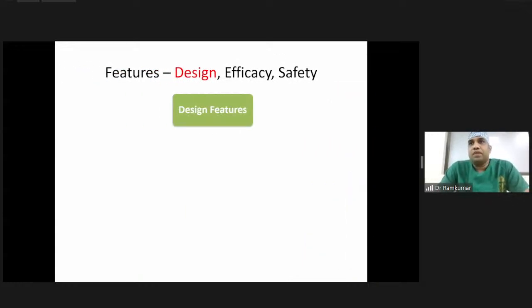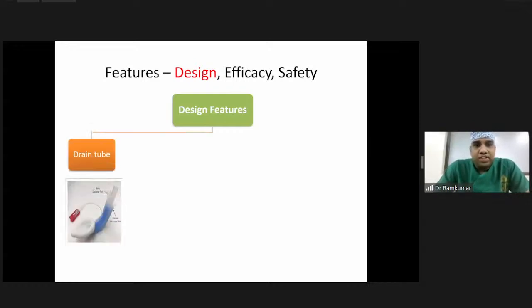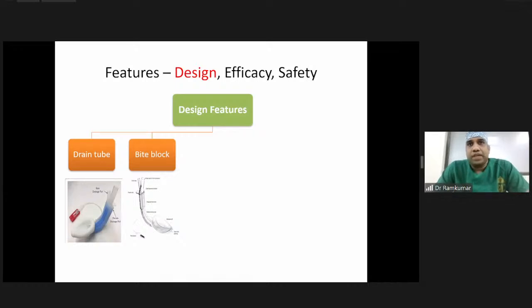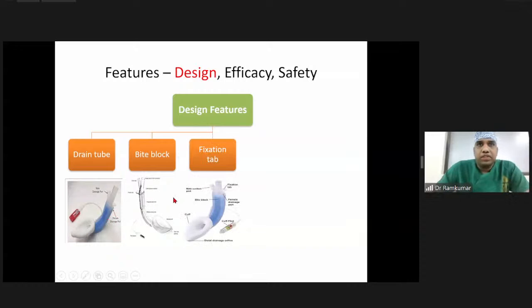What are the features that help to achieve this? Very useful. Coming to the design features, the drain tube: with the drain tube we can reduce the risk of aspiration and reduce the risk of gastric insufflation. And next is the bite block. If the patient is in an inadequate plane, they tend to bite the supraglottic device, so it can cause an obstruction and they go into hypoventilation or hypoxia. So the bite block is a rigid material present at the upper end of the device, as shown here. This is a bite block here, and there's a bite block here, which is around the teeth area. They prevent occlusion of the supraglottic device when the patient is in an inadequate plane.